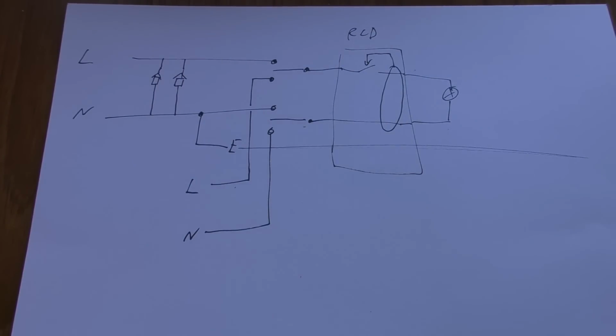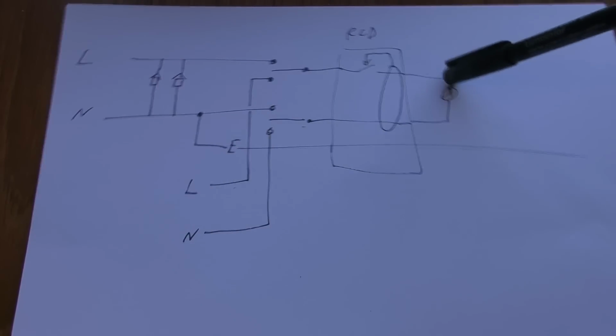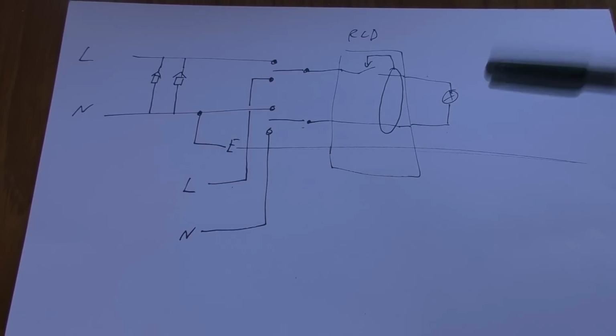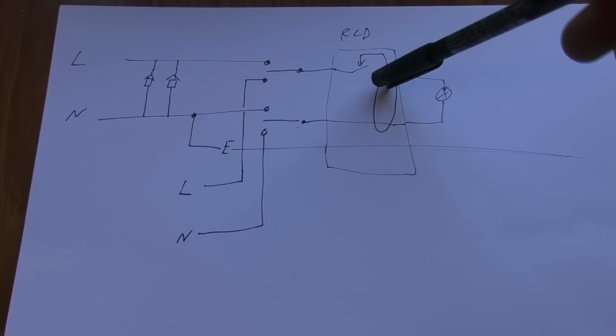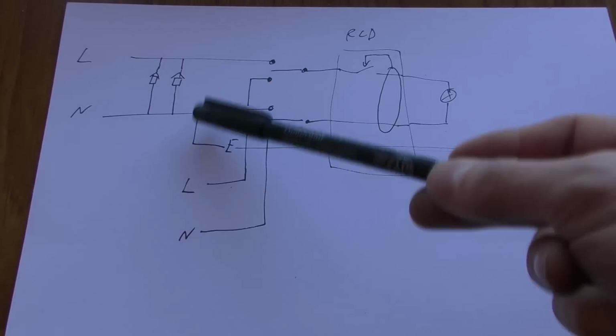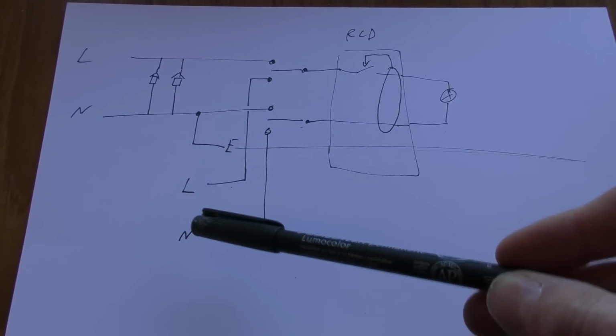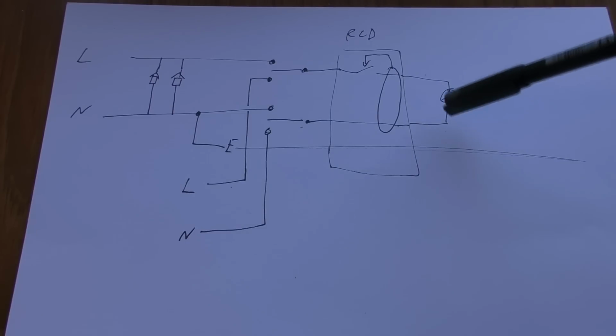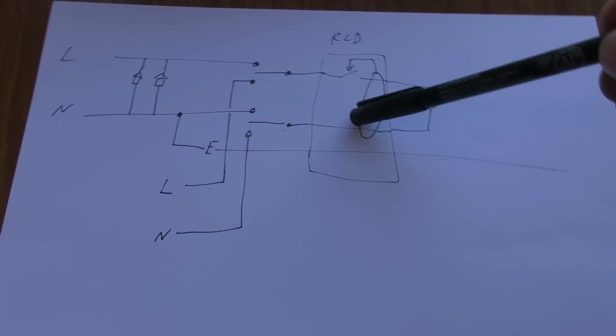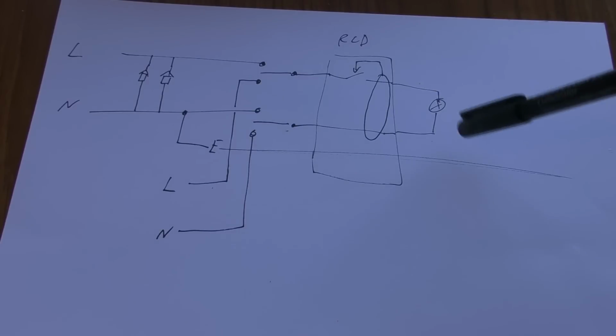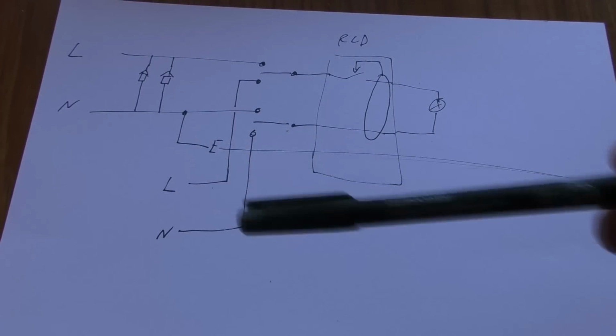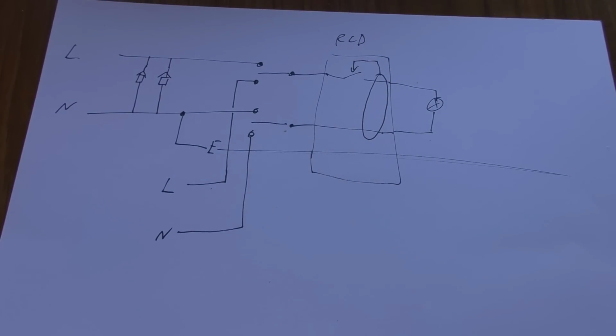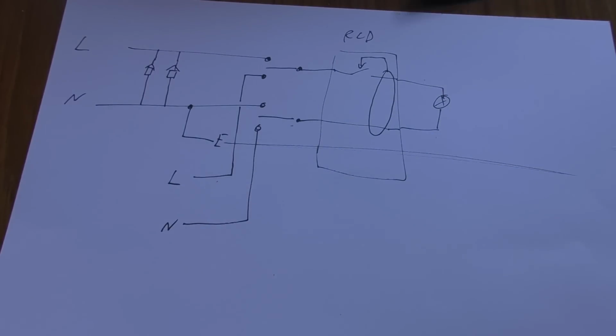Our supply is going through an RCD to our load, so obviously the idea about the RCD is that any leakage to earth from, say, a faulty appliance or water ingress or whatever will cause an imbalance in this current and trip the RCD. That relies on the fact the neutral is at roughly earth potential, either at the house or at the substation. Now, if we go to our backup supply, this is effectively completely floating, which means that any short between either of these sides and earth won't trip this RCD, because that leakage won't produce any significant imbalance. What will happen is that the average potential of the floating supply will just bounce up and down. So although it won't trip the RCD, safety-wise, because it's floating, there'll be negligible current flow. So it's probably not a particularly high safety risk.